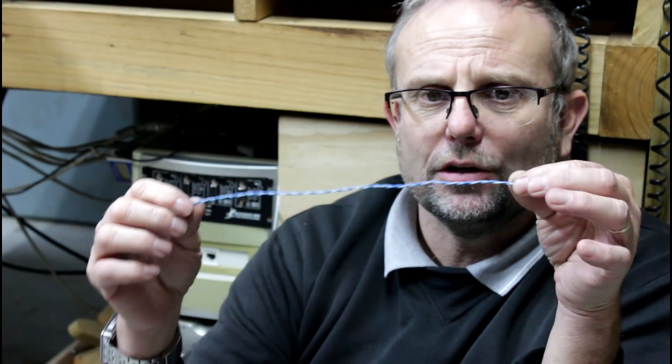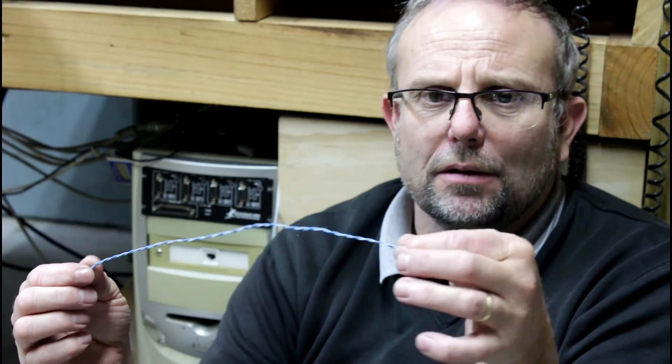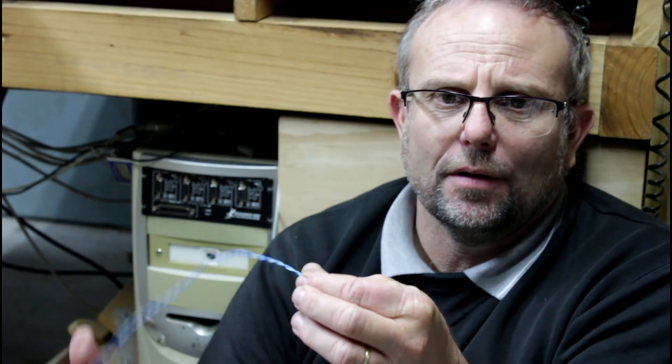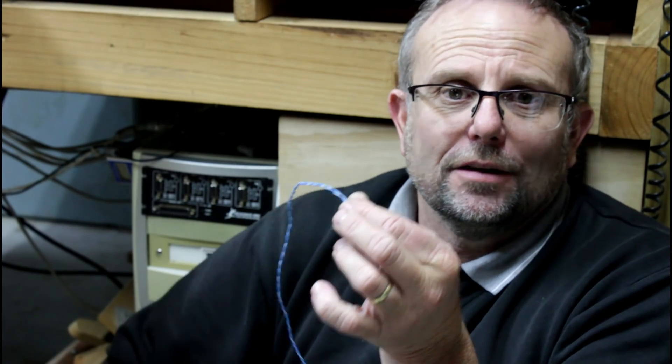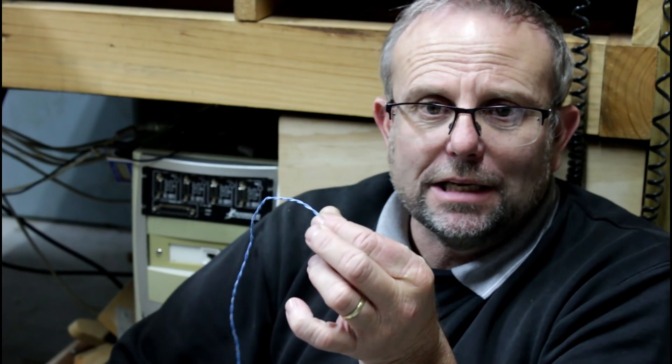The RS485 protocol is a balanced circuit. It needs a twisted pair of wires like this here. In theory it doesn't actually need to be shielded but it's not really going to hurt.